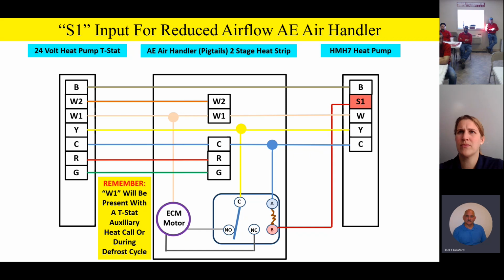ECM motors, they share the same type of technology. Only the standard ECM motor has just got speed taps on it, where the variable speed motor has a control board that you set up your airflow. But most of the time, if you've got properly sized ductwork, the units are so quiet you can hardly hear them. They're very, very quiet units, very efficient units as well. Good questions.